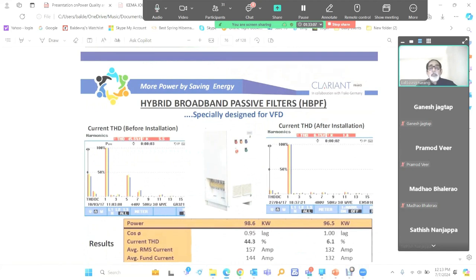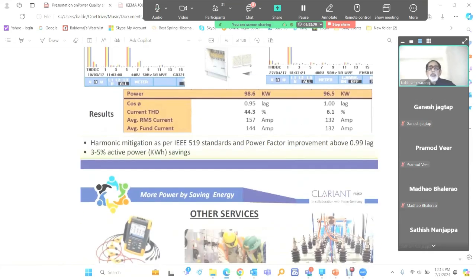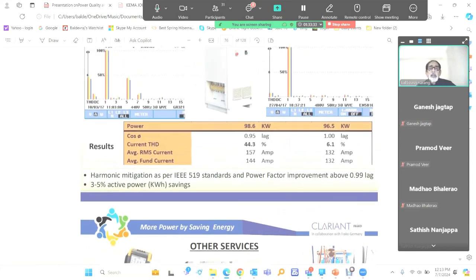This is hybrid broadband passive filter. Means like VFD itself, we can put this filter and control the harmonics at the generation point itself. Instead of putting it at the PCC or MCC, we can put it at the load itself across the VFD. VFD normally they have up to 60% harmonics. If they are using chokes inside, it is 40% or something. So then we bring it down to about 5-6%.